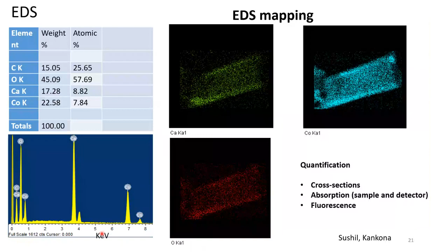If you look at a typical EELS spectrum, the y-axis is counts and the x-axis is energy loss. Here we are talking about electron volts. Okay, I forgot to mention in the previous slide that we were talking about kilo electron volts. Resolution in EDS is not really good. We are talking about something like 150 to 200 eV spectral resolution. On the other hand, here we are talking about 1 electron volt. With the best microscope, you can have about 1 electron volt spectral resolution, and monochromators can improve this resolution further.